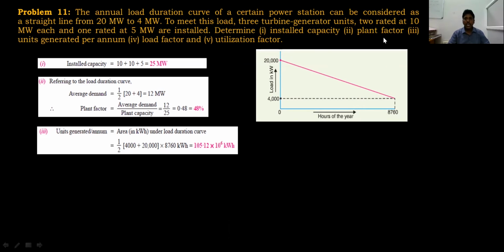And next one is plant capacity factor. Plant capacity factor is equal to number of units generated per year divided by plant capacity into 8760 hours. Here the number of units generated per year is 105.12 into 10 power 6, divided by the plant capacity, meaning installed capacity, which is 25 megawatts. Therefore, dividing by 25 megawatts into 8760 will give you the plant capacity factor.